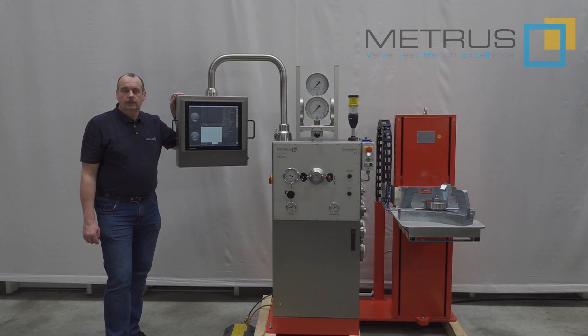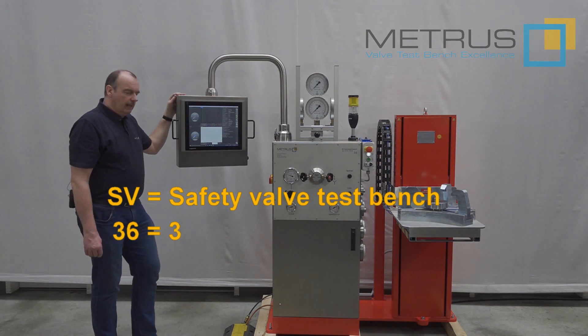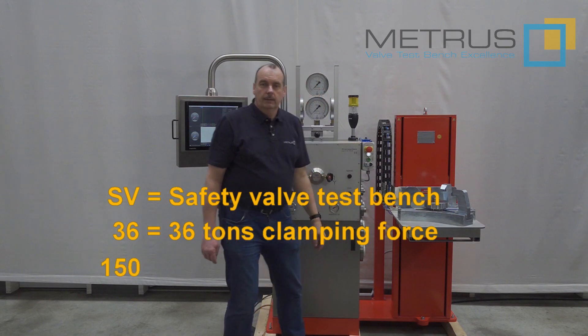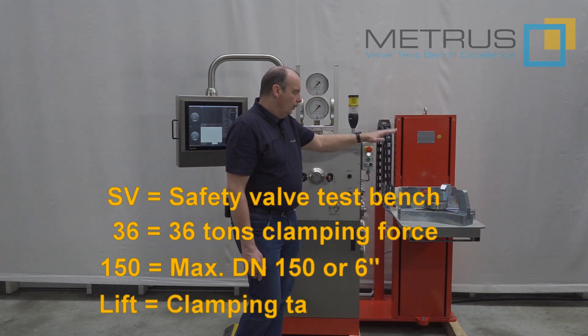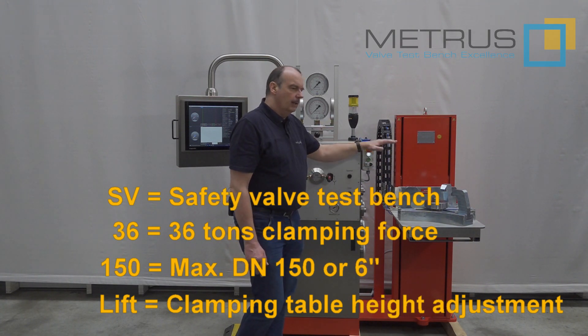Today I would like to introduce one of our newest developments, the safety relief valve test bench SV-36-150 lift. SV stands for safety relief valve test bench. 36 means we have a maximum clamping force of 36 tons on the clamping table. 150 means the maximum flange diameter I can clamp on this table is DN 150 or 6 inch. And lift means we have the possibility to move the clamping table up and down in accordance to the height of the safety valve I would like to test.